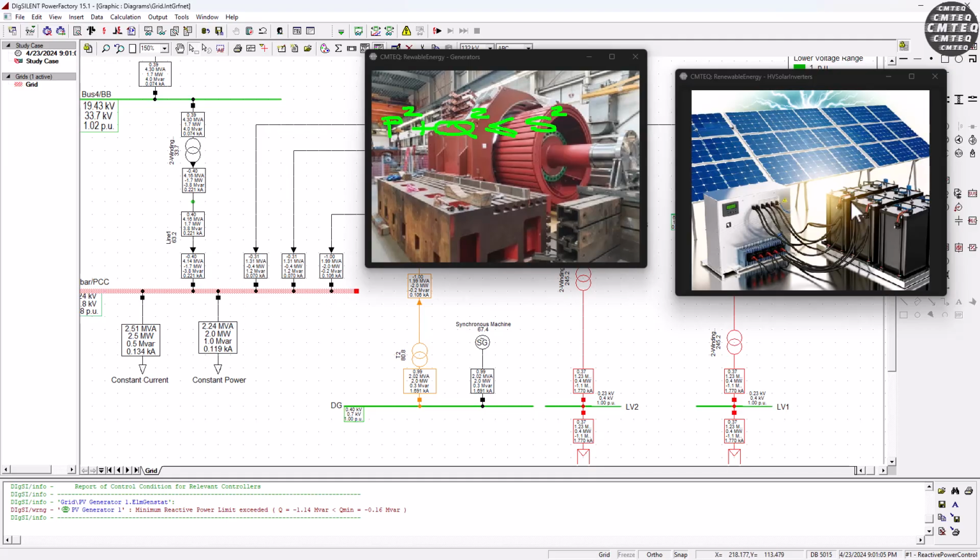So it doesn't care whatever the PV plant or the synchronous machine is doing to handle that. That is not the grid's problem. The grid just wants to make sure that the plant or the synchronous machine here can inject or absorb reactive power within the defined envelope safely and predictably. That's what the grid is waiting to see from both these elements.